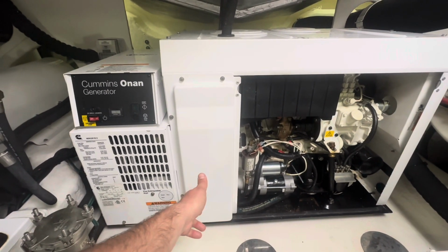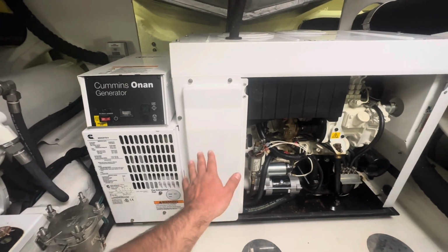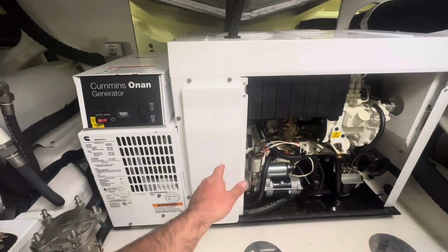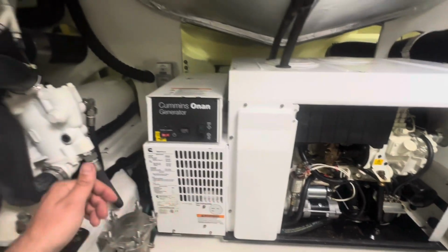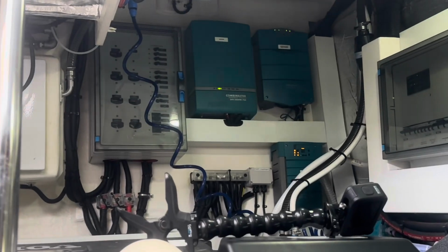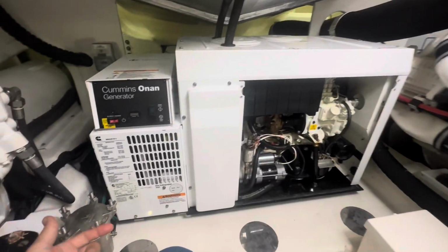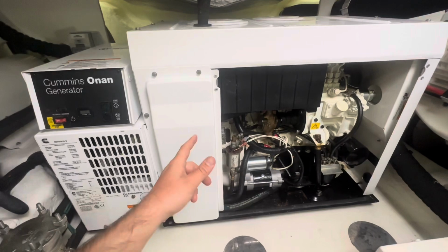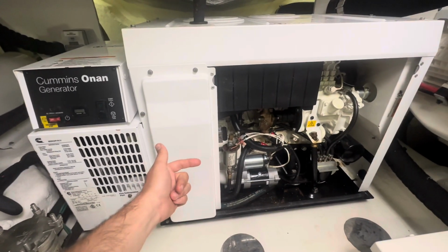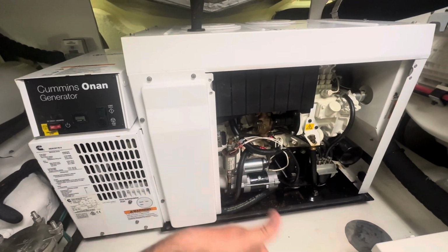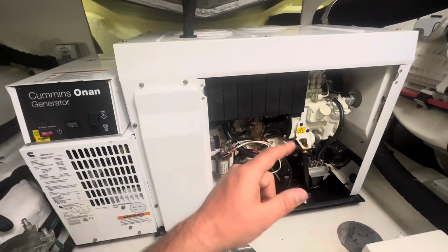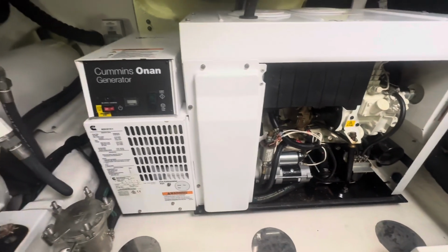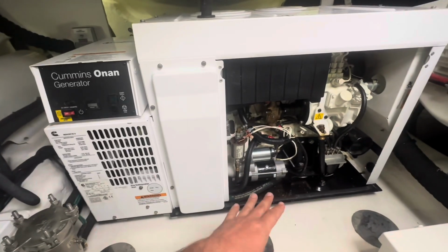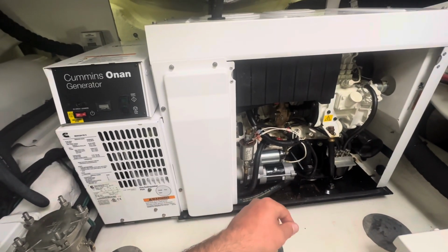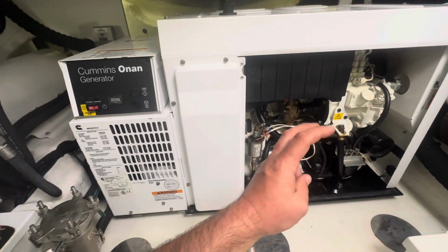The first thought that comes to mind with a high battery voltage code is either the batteries are being overcharged by one of those chargers, indicating a bad charger, or we have a voltage regulator going bad on the alternator side of the generator that charges its own batteries. So I was tossing between the two of those, trying to figure out why we were getting too high of voltage.